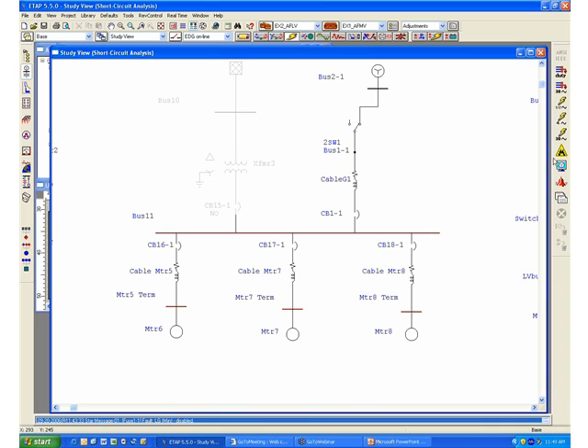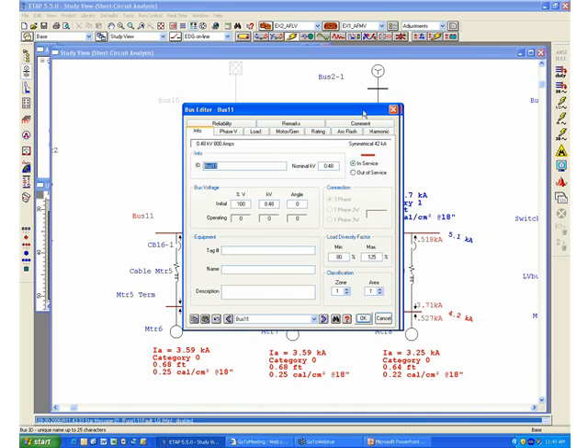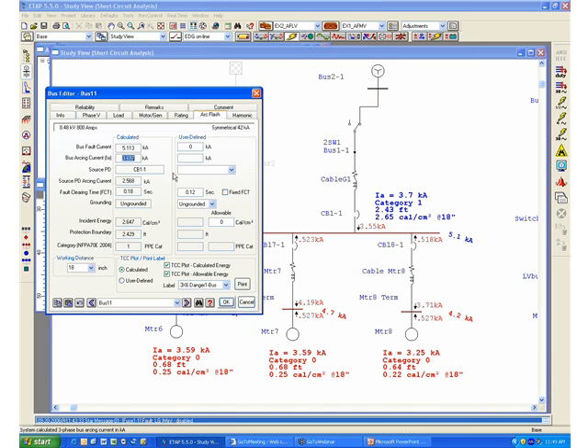if you rerun the study at this point, you will be able to see that the program has actually automatically determined now this to be an ungrounded system, and therefore that would also increase the amount of incident energy released in the system.